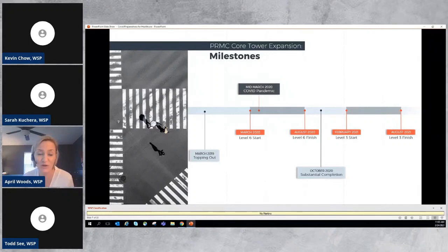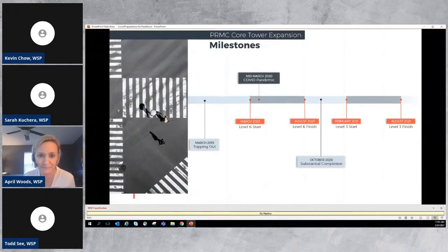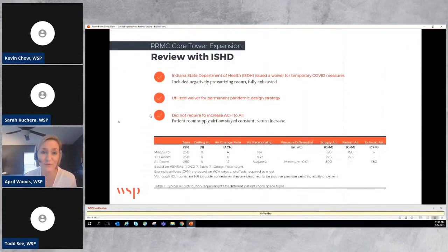In October 2020, the tower was substantially complete, and then almost immediately we started planning for the level 3 build out, which would also include pandemic provisions. And so part of that was really reviewing first with the Indiana Department of Health. So the first thing we looked at was the waiver that they had issued for the temporary COVID measures, which really included negatively pressurized rooms that were fully exhausted. And we were really able to utilize this waiver for our permanent strategy.